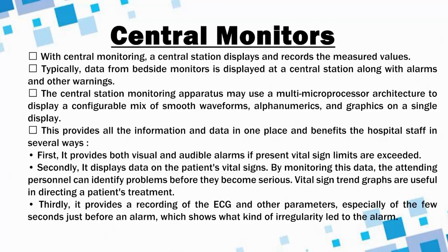The central station monitoring apparatus may use a multi-microprocessor architecture to display a configurable mix of smooth waveforms, alphanumerics, and graphics on a single display. This provides all the information and data in one place and benefits the hospital staff in several ways.